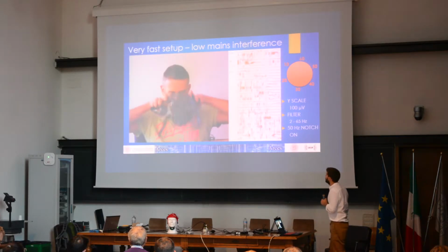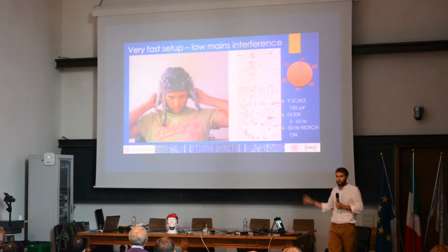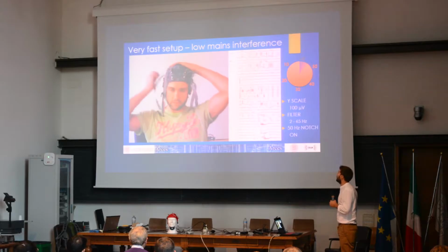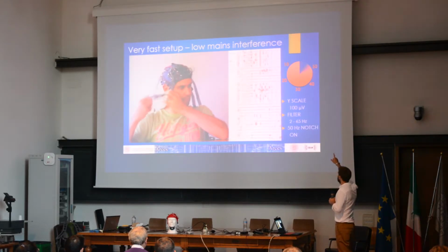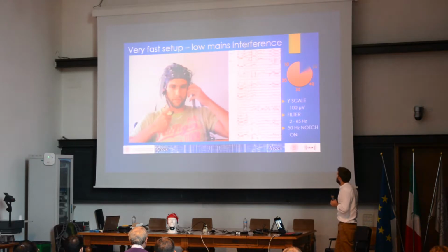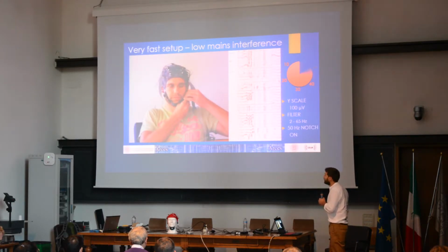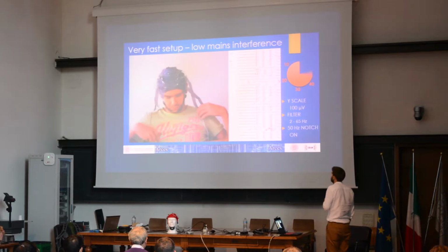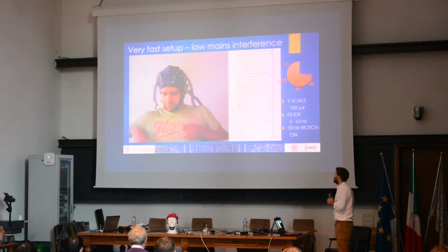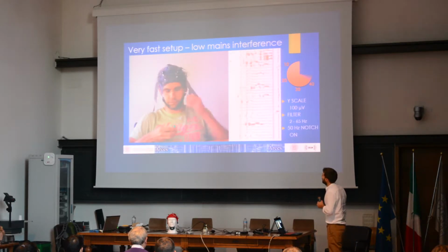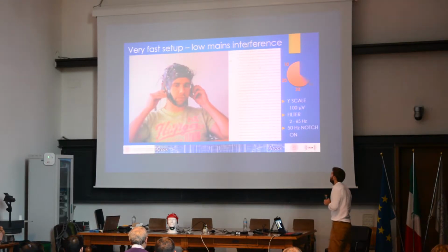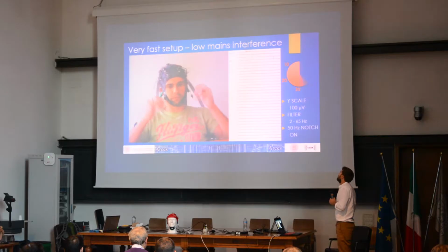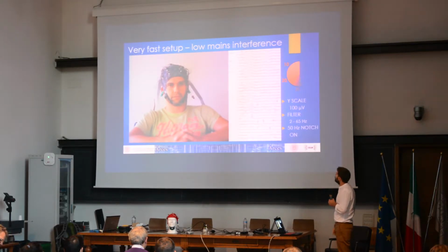So here I would like to show you a brief video. This is one of my colleagues putting on the cap by himself. On the right, you can see a countdown, and in more or less 1 minute, the system starts to work. This is the ground and reference contact. In this case, we have a notch filter to remove the 50 Hertz.